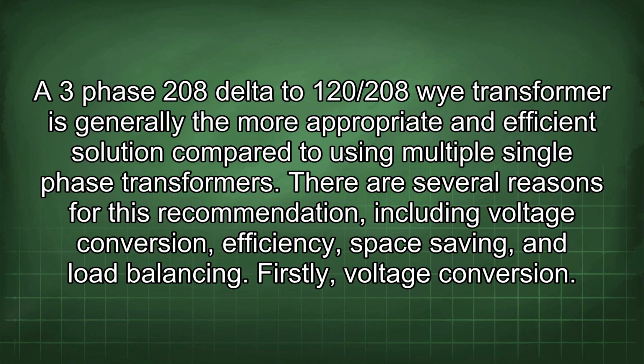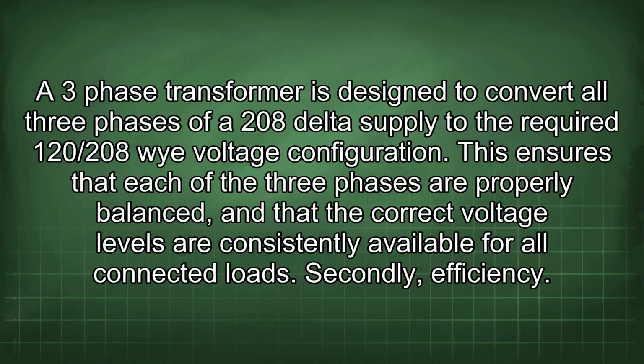Firstly, voltage conversion. A three-phase transformer is designed to convert all three phases of a 208 delta supply to the required 120/208Y voltage configuration. This ensures that each of the three phases are properly balanced and that the correct voltage levels are consistently available for all connected loads.